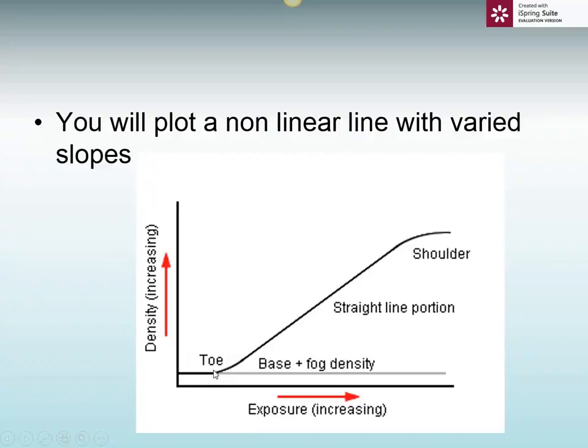As the exposure starts going up, then you start having the responsiveness. With a piece of film, if you don't use enough radiation, the density will be low. If you use more radiation, the density will increase. If you use too much radiation, then of course it's going to taper off. It's what we call the shoulder. In essence, what you're doing with something like this is saying when it really starts responding. On the other hand, this part here is telling you the degree of contrast. In other words, the exposure goes up, but there's just this gradual increase.